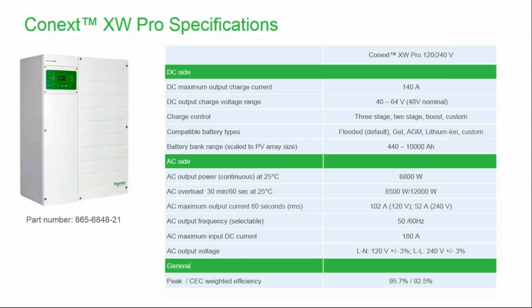The second thing that we can do is we can take AC provided by a generator or the grid and charge the battery. And in that way, we're an AC to DC converter. We can do 3-stage charging, which is optimum for flooded lead acid batteries. We can charge up to 140 amps, and we can basically charge all of the different technologies using either the flooded, gel, AGM, lithium ion, or custom setting.